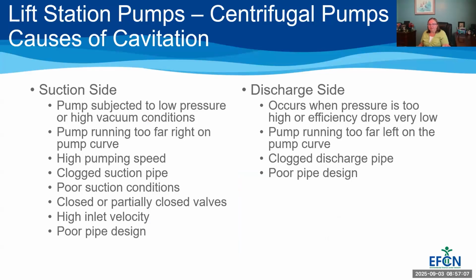So what can cause cavitation? On your suction side, if your pressure is too low, if you're running at high speeds, if you have a clogged suction pipe, you have poor suction conditions, you have a partially closed valve, that's why I said we don't want to throttle valves, or you have poor pipe design, so probably not in a lift station, but in other situations you can have poor pipe design on your suction side. On your discharge side, if the pressure is too high, if the pump's running too far left on the pump curve, if there's clogged discharge pipe, or there's poor pipe design, so maybe your pipe's not sized right, or immediately there's a lot of elbows and T's and reducers, or things like that. It can cause the pressure to increase significantly. So all of those can cause cavitation.